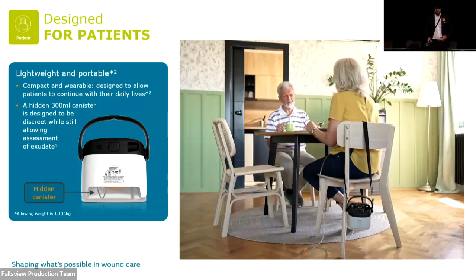So how we did it, as I said, in the canister, we call it discrete canister because it actually goes inside the pump. So from the front, you won't really see the exudate all the time. But from a clinician standpoint, I want to see the exudate, and you can see that from the back of the device, where you got a transparent window that you can see the level of the exudate. Whether it's on the 300 ml canister or on the 800 ml canister, you will always be able to see that quite easily and immediately.